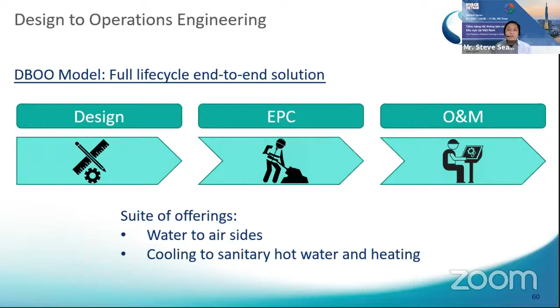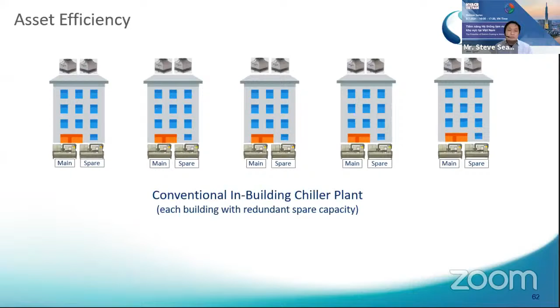Let us look at the key benefits of district cooling. One key benefit is asset efficiency, which leads to savings in capex and space due to using less equipment. Take a simple model: you have 5 buildings, each operating 1 chiller plus 1 spare. If you centralize the plant to serve all 5 buildings, you can reduce the number of spares, saving on both capex and space for your plant rooms as well as the cooling towers on the rooftop.